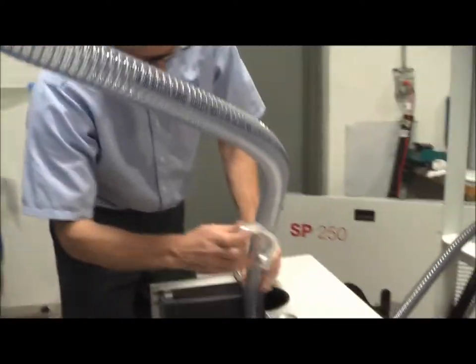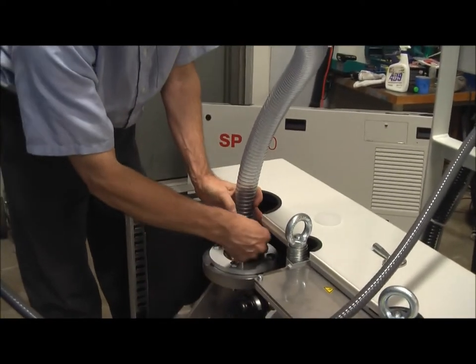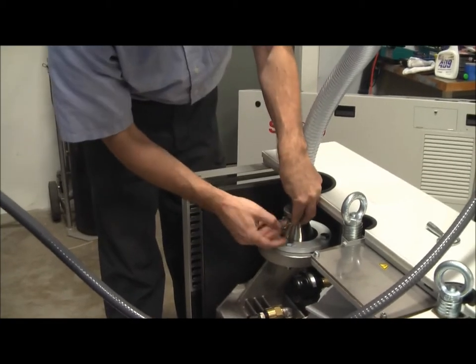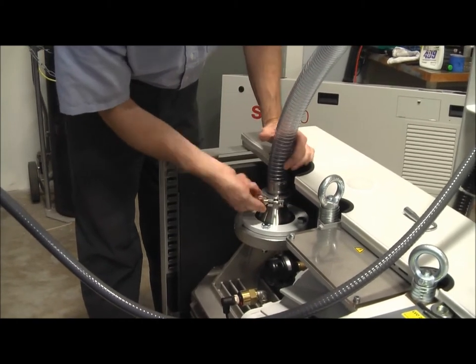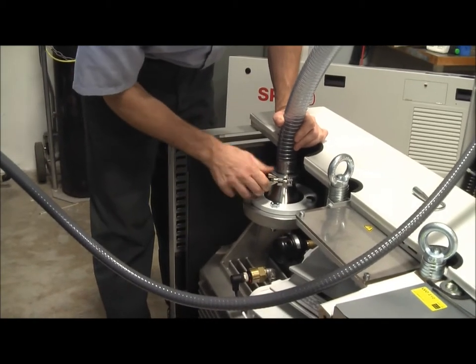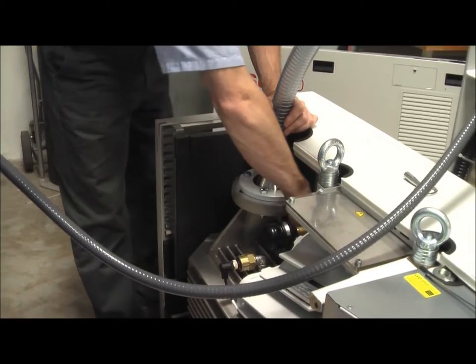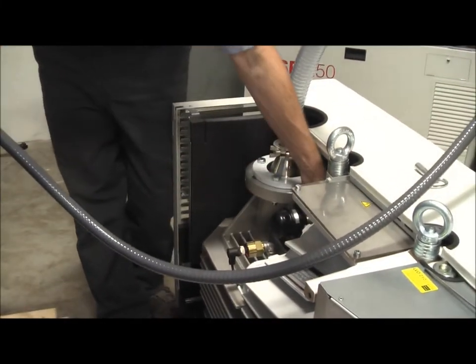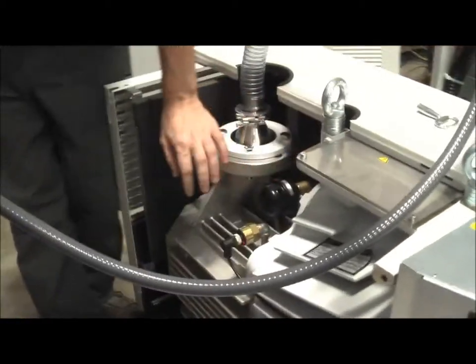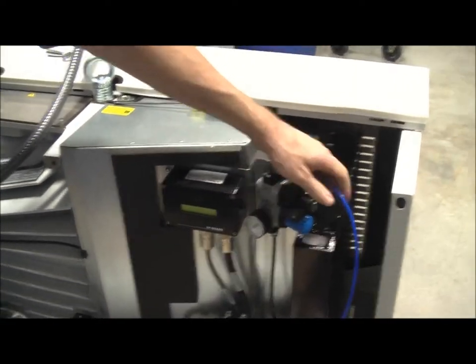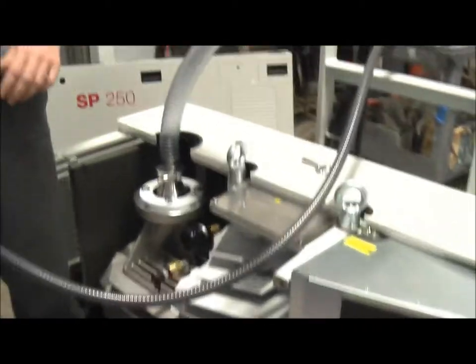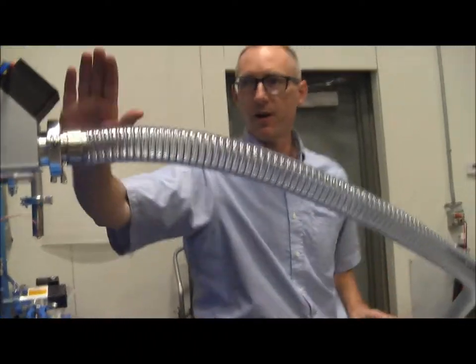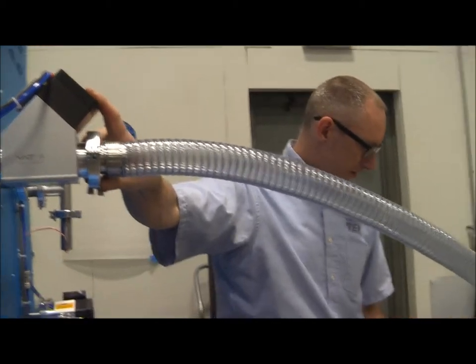We'll put on the hose here. Make sure our air purge is on. This is just our ballast that sucks in a little bit into the crankcase to keep the moisture out. This one's the gas purge for the bearings. So that's our provided air. We've got oil hooked up. The next step is, once we've got it all hooked up, we make sure we have our hose connected and our oven is not running so the valve is shut so that the pump won't have any load.